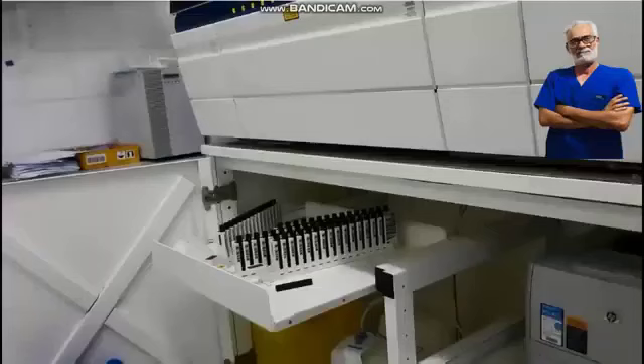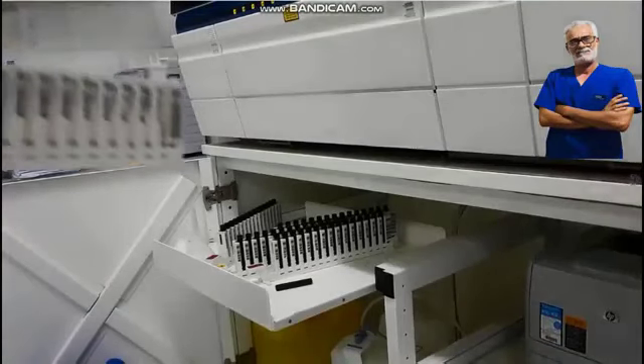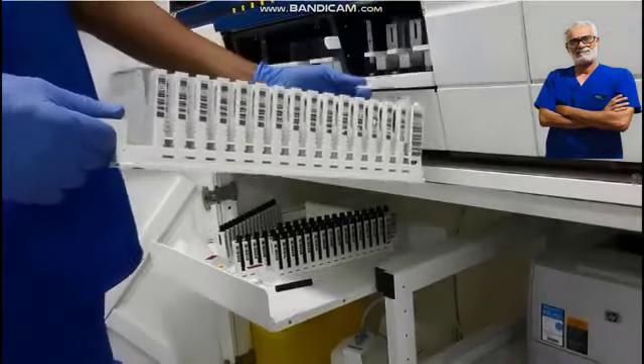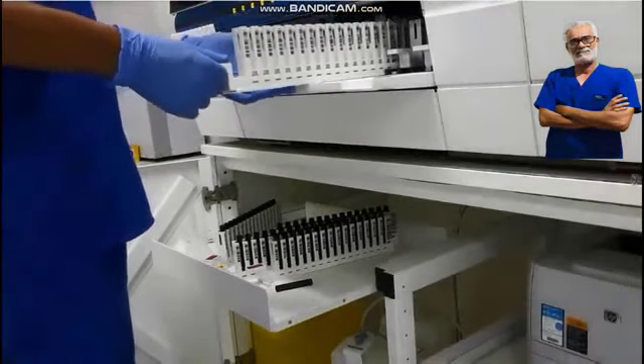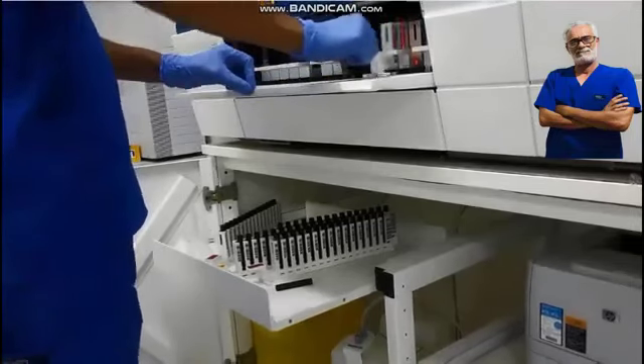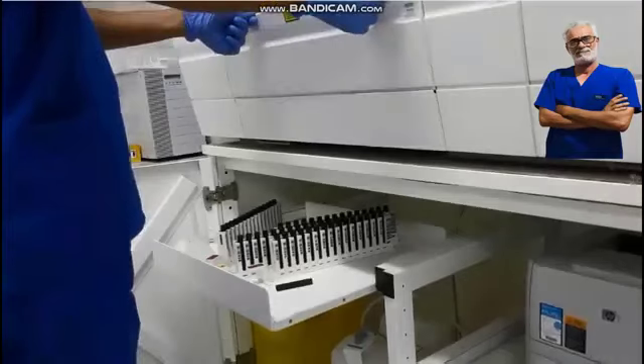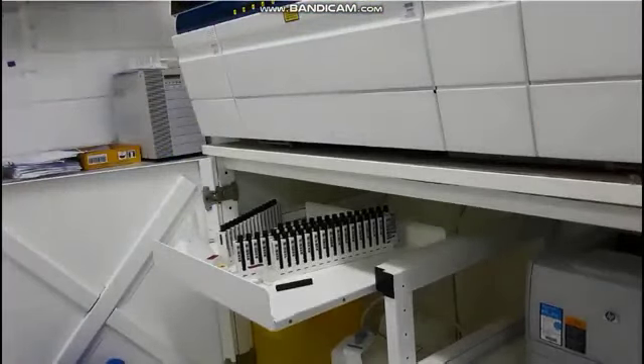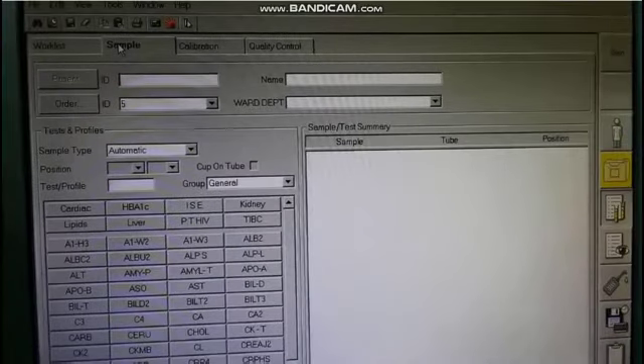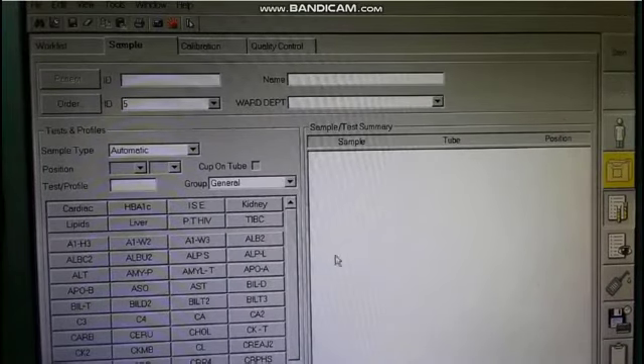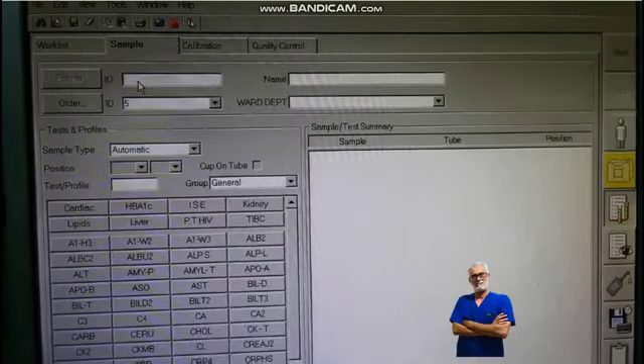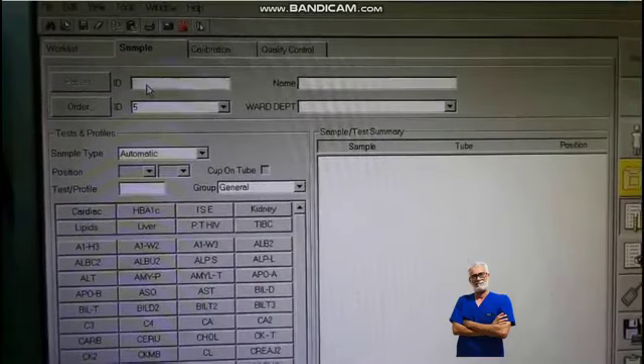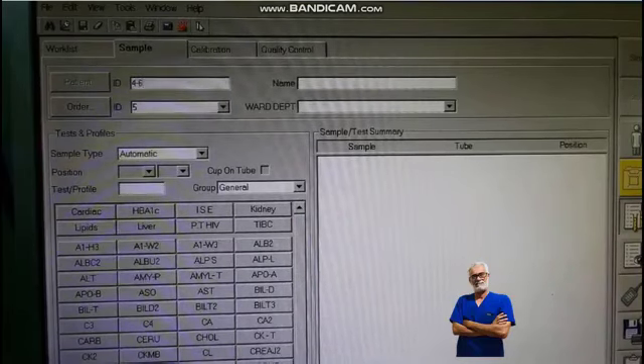Now that our samples are perfectly prepared and safely placed in the rack, we turn our attention to the computer software control unit. From the main dashboard of the system interface, we need to navigate directly to the Sample tab. This is effectively the heart of the entire operation. Please follow the screen movements very closely now. We begin the registration process by entering the patient's essential and primary information. First, we type in the unique patient ID number carefully, then we move to the next field to enter the patient's full name. It is extremely important to also include the date of birth and the gender, because the Integra 400 Plus system uses this specific data to determine the correct reference ranges for your final results.